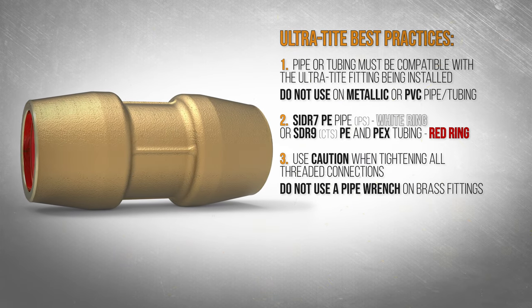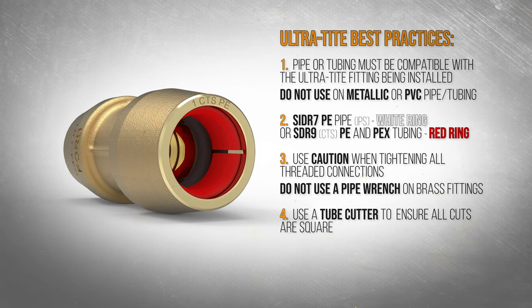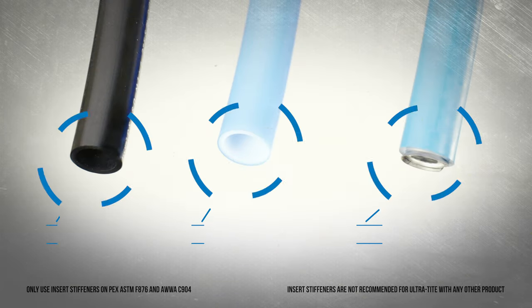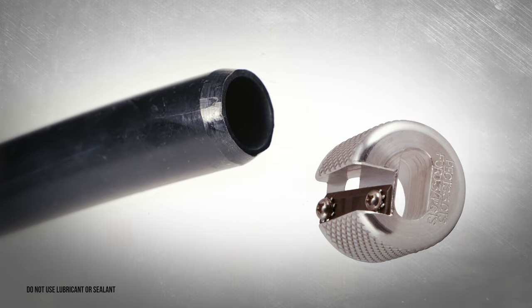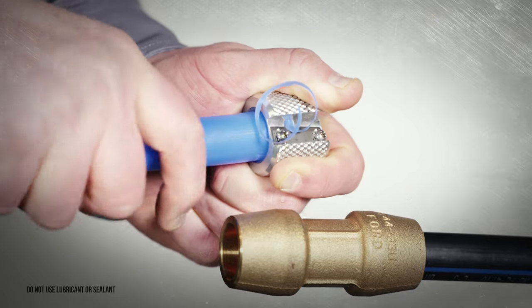Use caution when tightening all threaded connections. Use a tube cutter to ensure all cuts are square, and make sure the pipe or tubing is clean, round, and not nicked or cut. Ultra-Tite fittings do not require the use of an insert stiffener unless installing on PEX tubing meeting ASTM F876 and AWWA C904. Use a chamfer tool to bevel the end of the plastic pipe or tubing before making the connection to assist insertion and prevent O-ring damage.